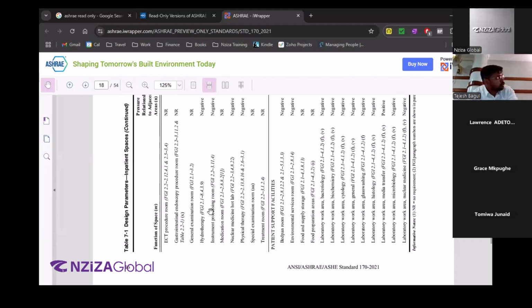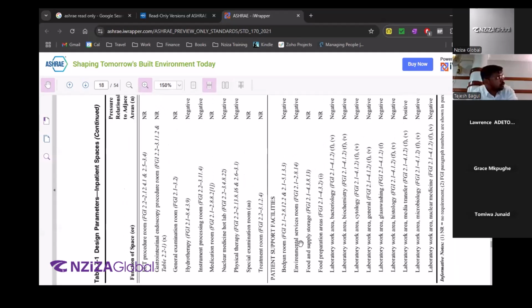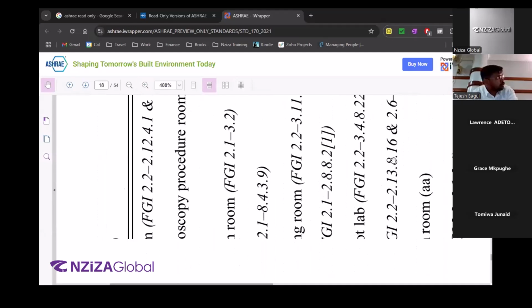From my presentation, if you check, you will have the operating rooms, the patient rooms, and the toilet rooms. You have to identify where that patient room, toilet room, operating room, whatever it is, is in this table. Then follow this row to find out the relevant parameters with that particular type. Then find out the relationship to adjacent areas. Next parameter. So basically, if you have areas, the pressure relation.